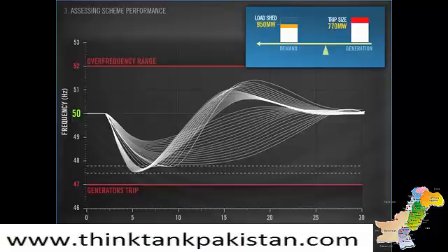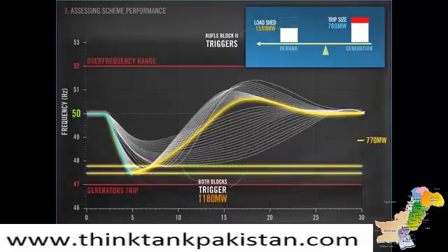Notice that although the generation loss is increasing, the load shed hasn't changed. This is because the blocks are fixed. In this medium load example, you can see that although your maximum frequency is coming down, the minimum frequency is continuing to drop. You're getting closer to triggering AUFLS Block 2. In the simulation, 770 megawatts was the last size event that triggered only Block 1. An increase in trip size of only 10 megawatts of generation triggers AUFLS Block 2.